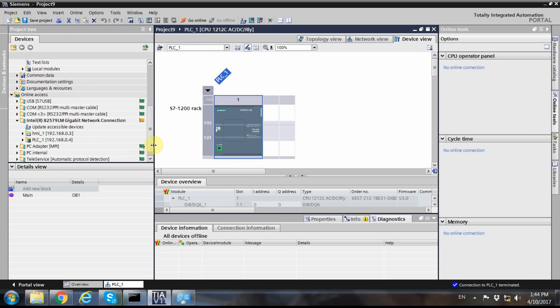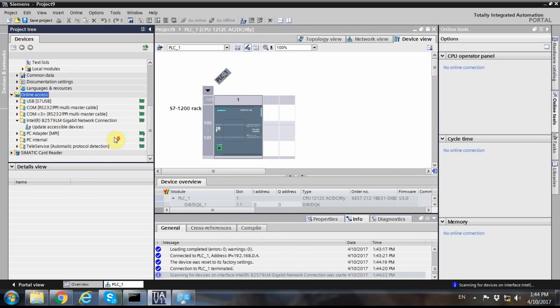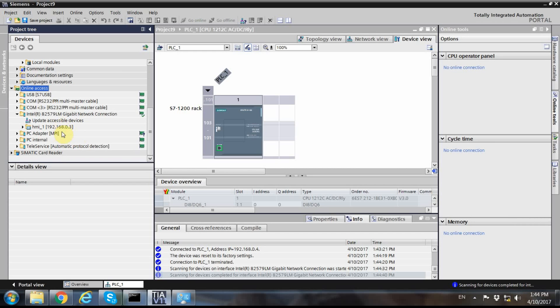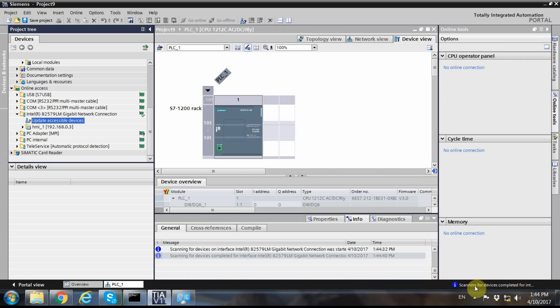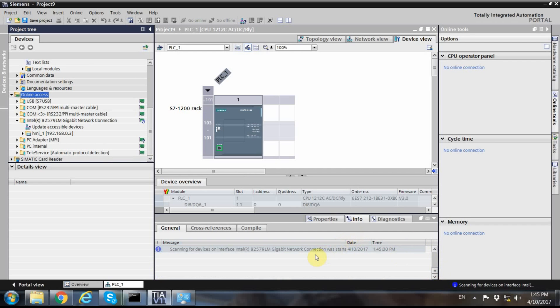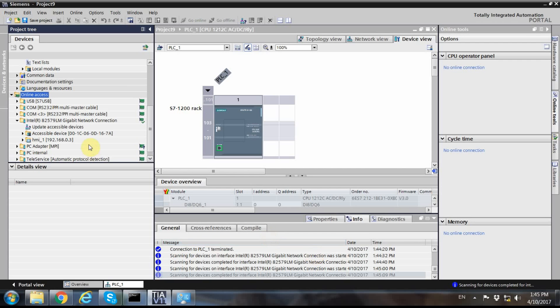If I reset the PLC to factory settings and reset the IP address — which is only possible in online mode — the IP address of the PLC will be removed and I'll lose my connection. Now if I refresh the list of accessible devices, the PLC appears this time with its MAC address instead of an IP address, because it no longer has one assigned.